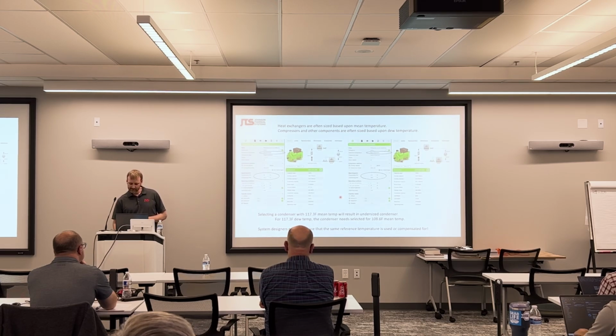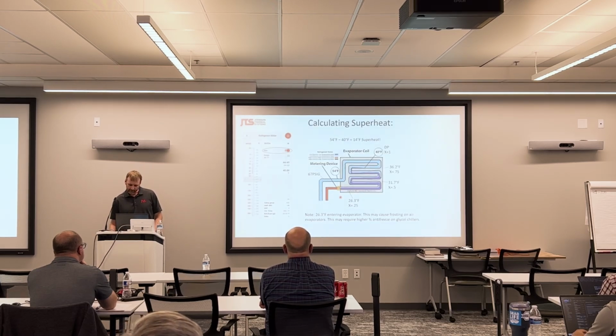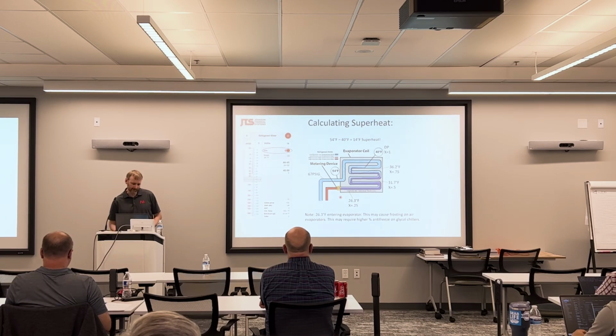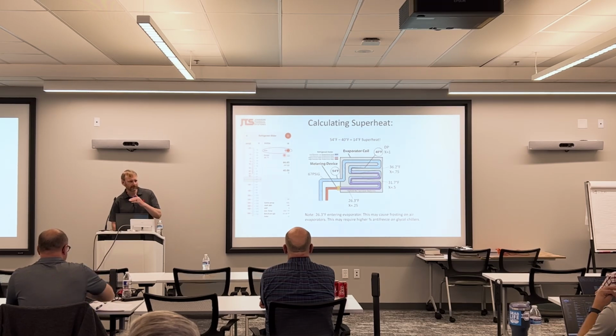So system designers need to ensure that you always reference the same temperature, or you can compensate by adding temperature to the compressor selection. Calculating superheat on glide refrigerant is pretty much the same as what we're used to. The biggest difference is that you have to reference dew point. As mentioned, refrigerant will increase in temperature the closer you get to the dew point. And what you're trying to measure is superheat that's generated beyond the dew zone.